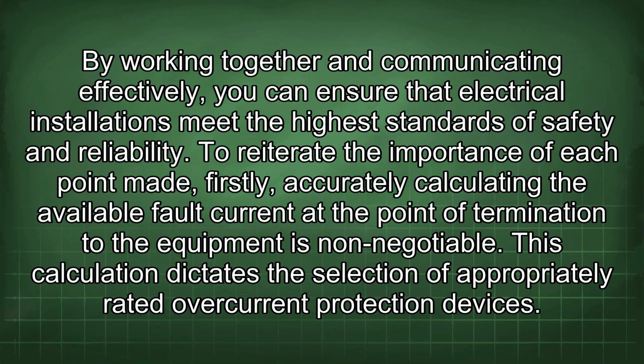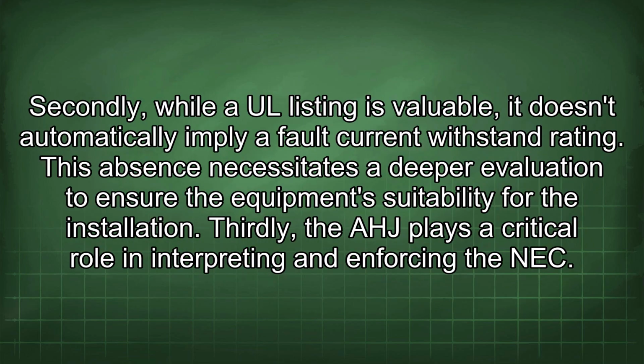To reiterate the importance of each point made, firstly, accurately calculating the available fault current at the point of termination to the equipment is non-negotiable. This calculation dictates the selection of appropriately rated overcurrent protection devices. Secondly, while a UL listing is valuable, it doesn't automatically imply a fault current withstand rating. This absence necessitates a deeper evaluation to ensure the equipment's suitability for the installation.